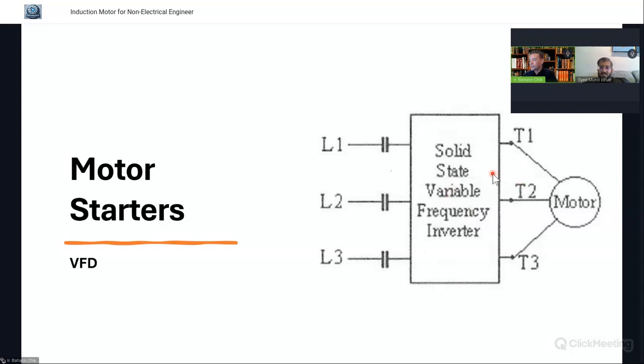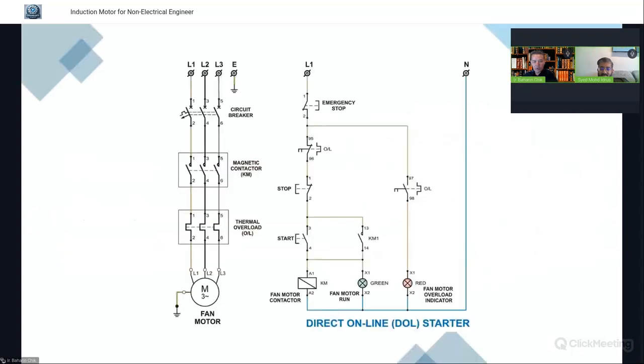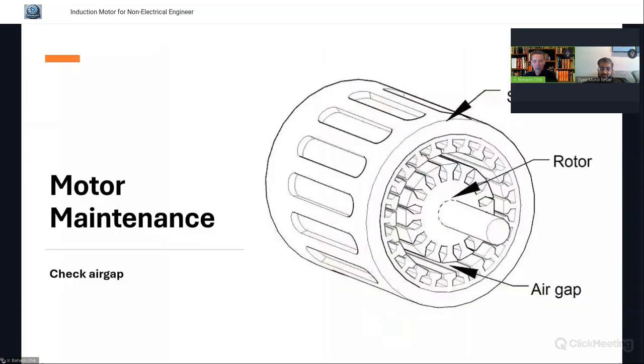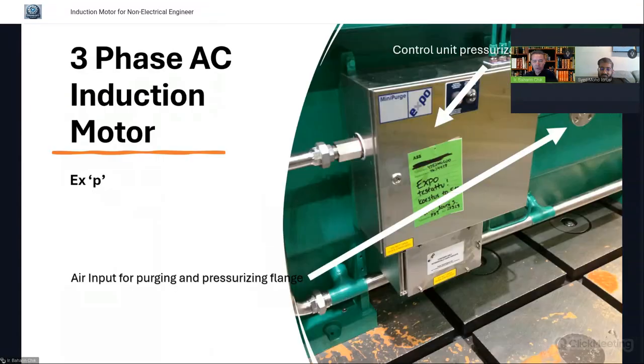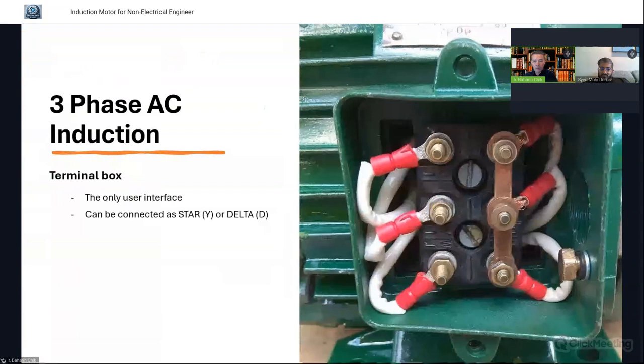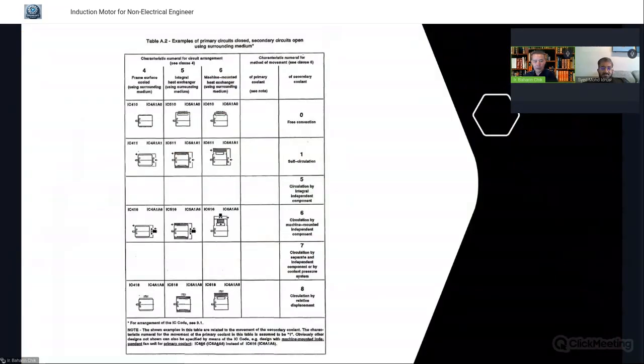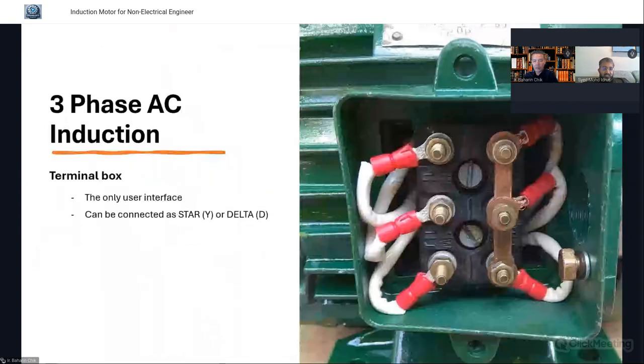Alright, understood. The next question asks: how to determine the rotation of the motor from the terminal connection? Normally before we do the solo run, we do this test as well. Let me go back. For example, here there is a picture of the terminals. Now if we connect U1 to phase red, yellow, blue, then it turns clockwise, let's say. Then if we switch over one of the terminals, it may turn the other way around.